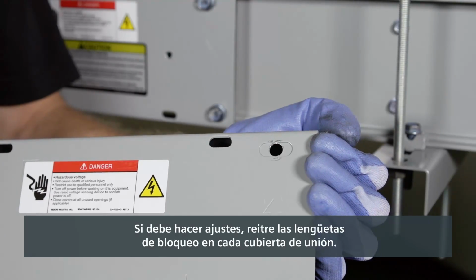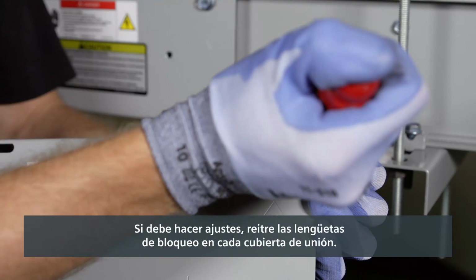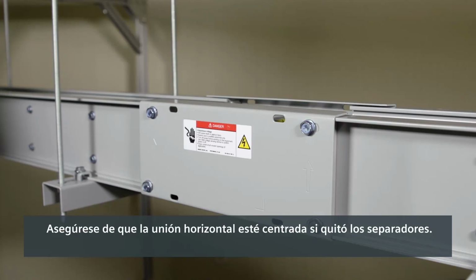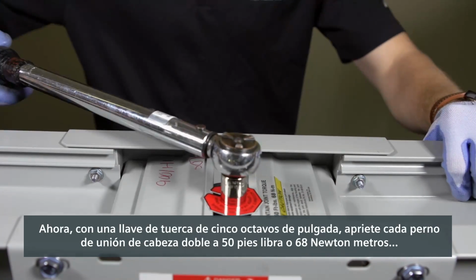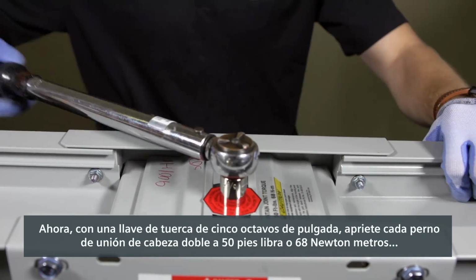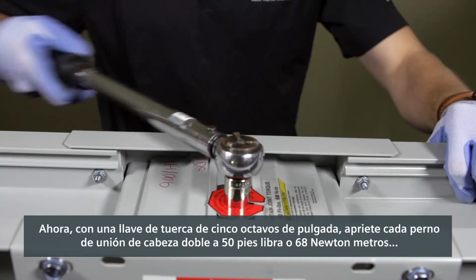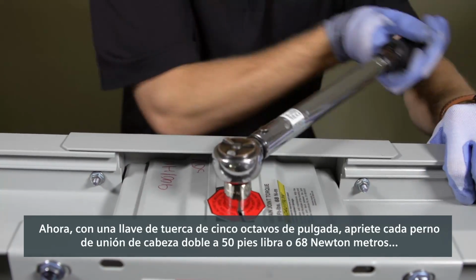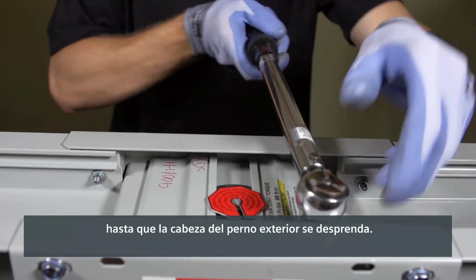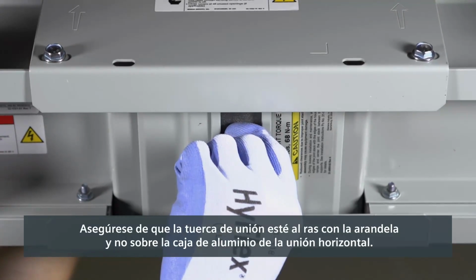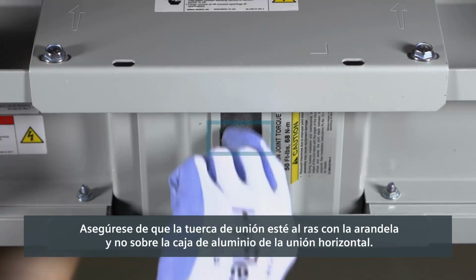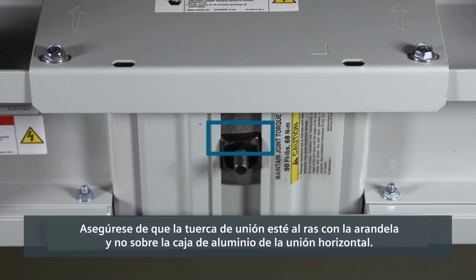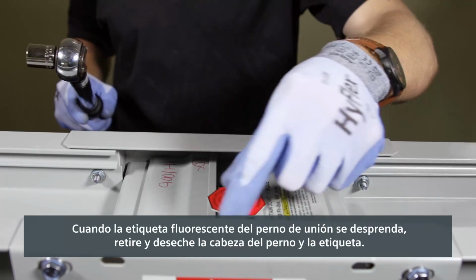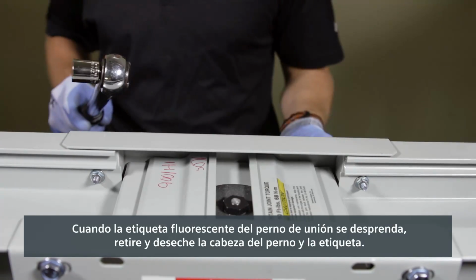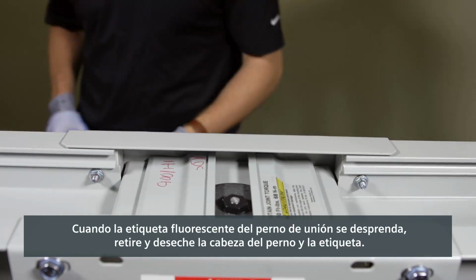If you need to make adjustments, remove the appropriate knockout tabs in each joint cover. Be sure the joint stack is centered if knockouts are removed. Now, with a 5/8 inch socket wrench, tighten each double-headed joint bolt to 50 foot-pounds, or 68 newton-meters, until the outer bolt head shears off. Ensure the joint nut is flush with the washer and not riding on the aluminum enclosure of the joint stack. When the red fluorescent joint bolt label detaches, remove and discard the bolt head and label.